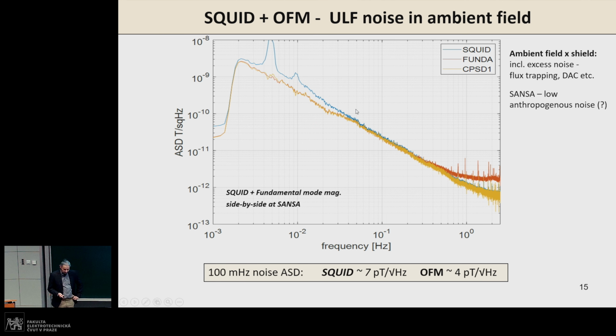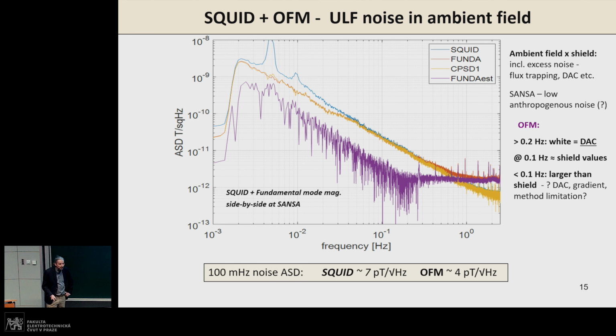And if we calculate the cross-power spectra, we have the yellow line. If we subtract, we can see the noise of our orthogonal fluxgate. And the most interesting thing is that finally we can see the white noise of our DAC compensation. The DAC compensates most of the stable bias in the field so that we can expand the range. So this is the white noise of our DAC, and here we can see a 1/f slope, which combines the data acquisition and sensor noise.